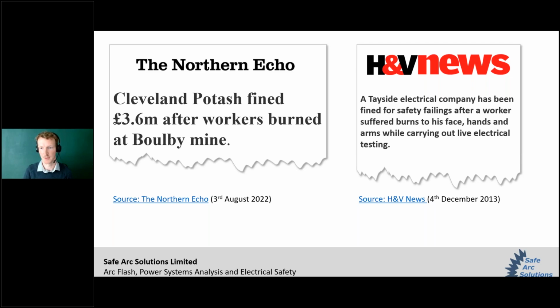Here are a couple of examples from newspaper stories, as arc flash occasionally makes it into the headlines. This one, from the Northern Echo, reported on two separate arc flash incidents over a couple of years at the same mining site in the northeast of England. One incident involved an electrical worker tidying up inside a live high voltage panel, who unfortunately brought a vacuum cleaner nozzle into contact with the live conductors. That inadvertent contact set off an arc flash event. Thankfully he survived, but he suffered terrible burn injuries, requiring two weeks of intensive care and numerous skin graft operations to repair deep burns to his face, hands, and torso. Sadly those injuries proved life-changing — he's no longer able to do his previous role and has had to move into an office-based role.